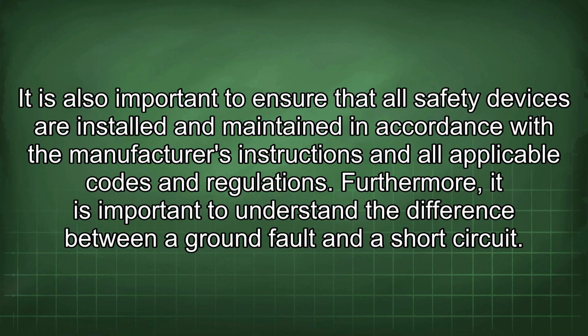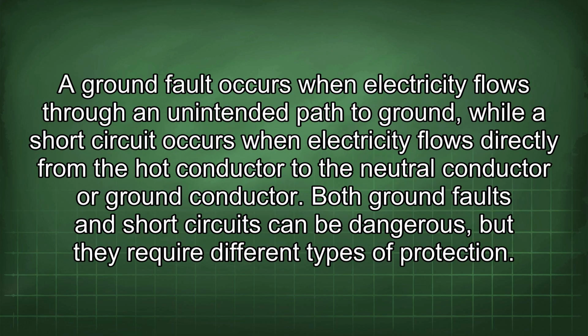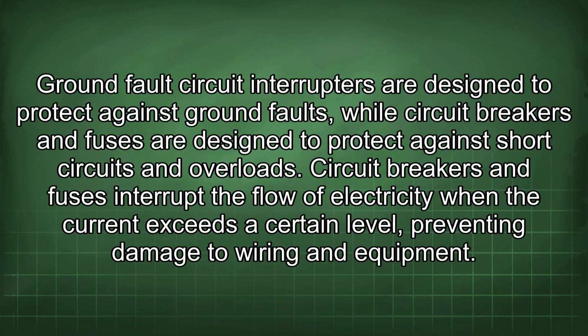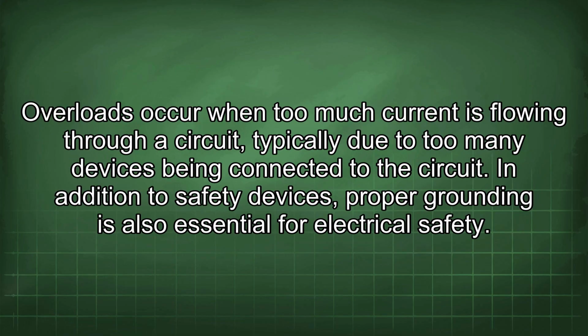Furthermore, it is important to understand the difference between a ground fault and a short circuit. A ground fault occurs when electricity flows through an unintended path to ground, while a short circuit occurs when electricity flows directly from the hot conductor to the neutral conductor or ground conductor. Both ground faults and short circuits can be dangerous, but they require different types of protection. Ground fault circuit interrupters are designed to protect against ground faults, while circuit breakers and fuses are designed to protect against short circuits and overloads. Circuit breakers and fuses interrupt the flow of electricity when the current exceeds a certain level, preventing damage to wiring and equipment. Overloads occur when too much current is flowing through a circuit, typically due to too many devices being connected to the circuit.